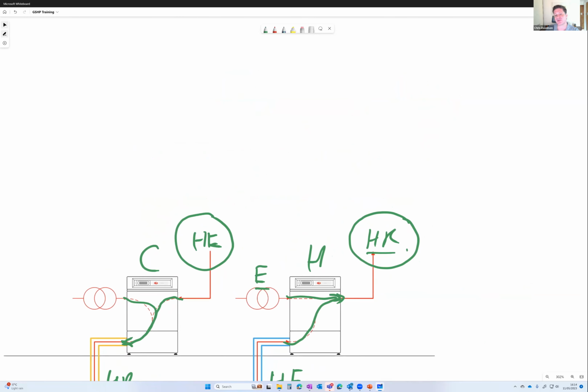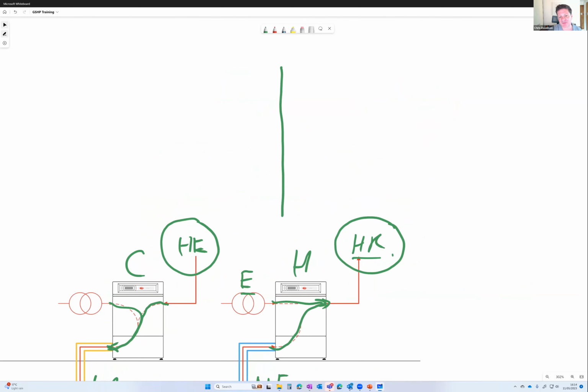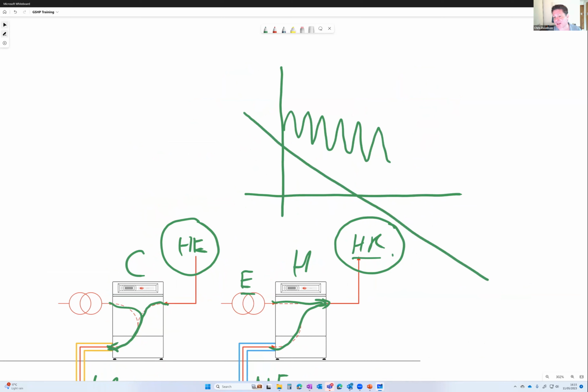So what do I mean by sustainability? If I draw a graph in a heating-only system on an annual basis of the temperature in that ground loop, it's going to decline slightly each year. What we don't want is for it to keep declining indefinitely. What we want is for it to tend to a limit, and that limit needs to be within the efficient operation range for that heat pump.